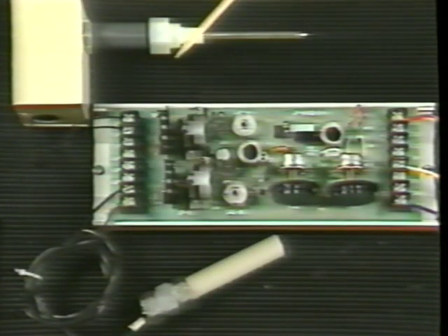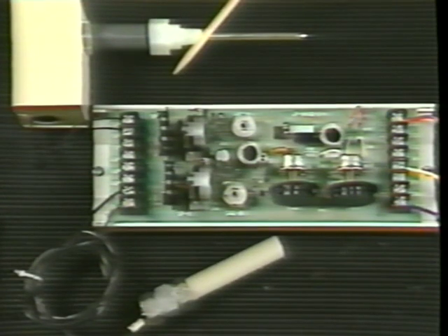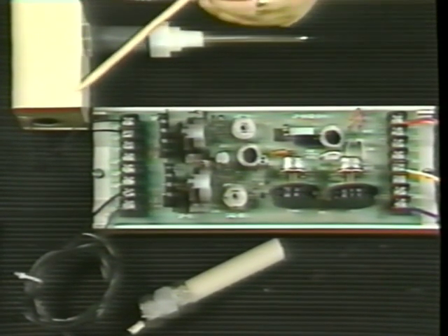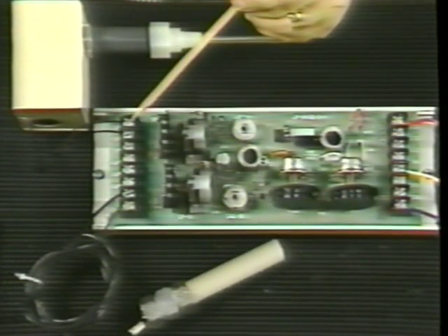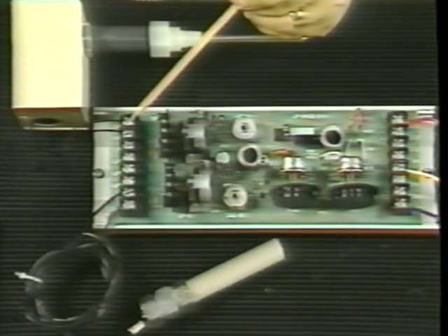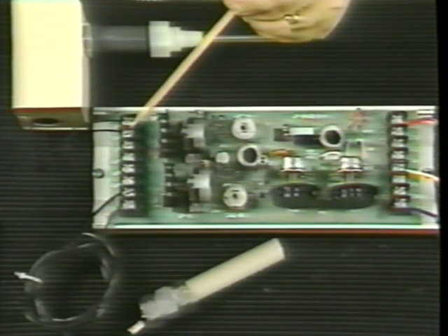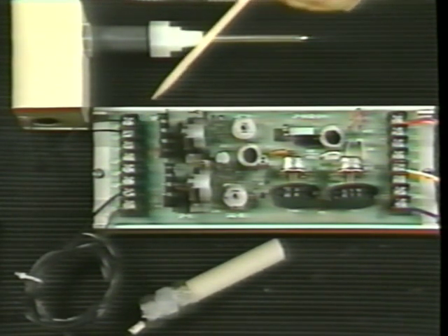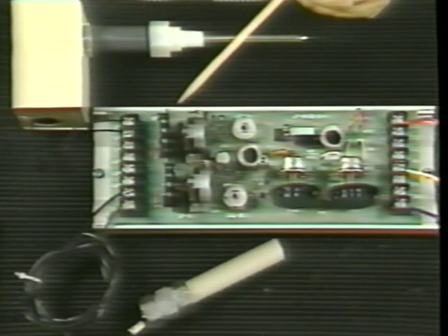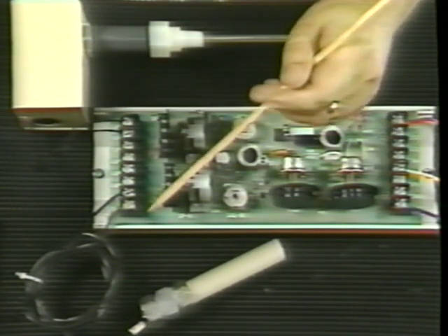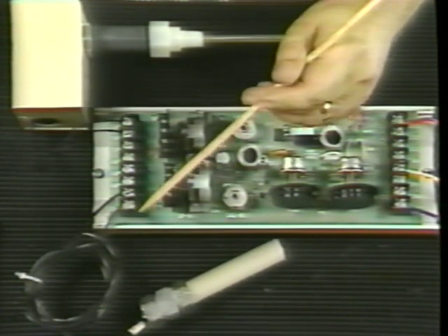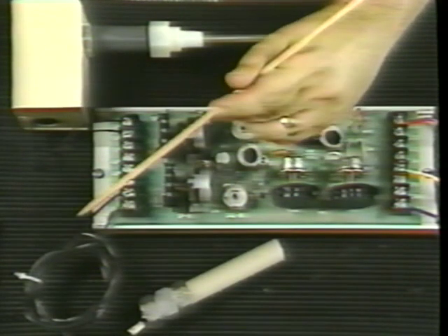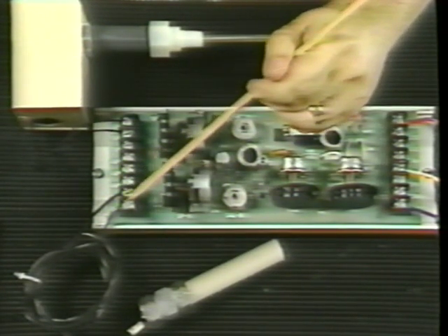When the CP8102 is used as a single input controller, the control sensor will be wired through its two leads to terminals ISA, ISA. The details on wire length and wire gauge are contained in the electronics section of our green catalog. When the controller is used as a dual input, that is, with a secondary input for reset, that secondary sensor is wired to ISB, ISB.